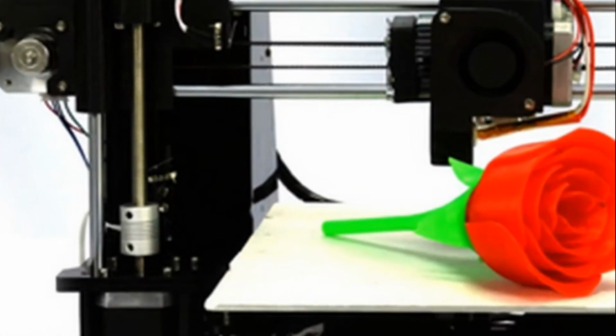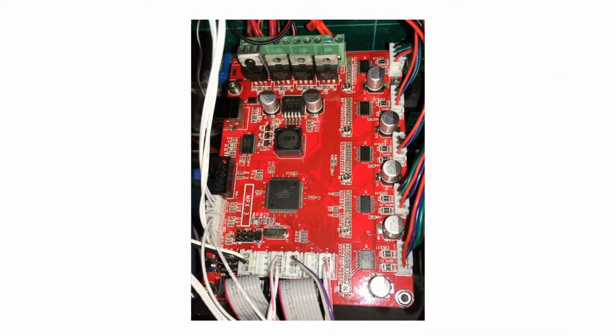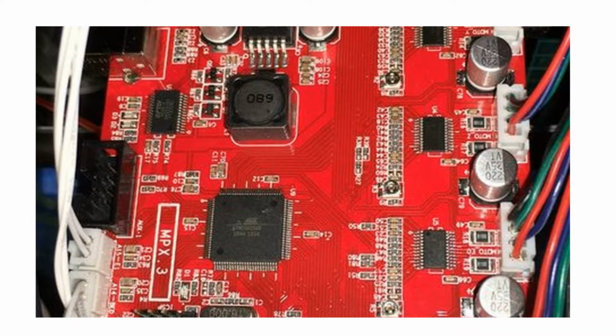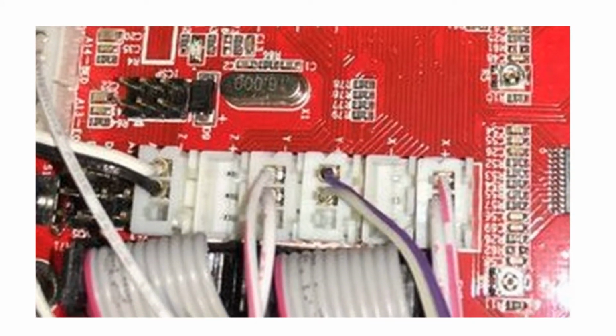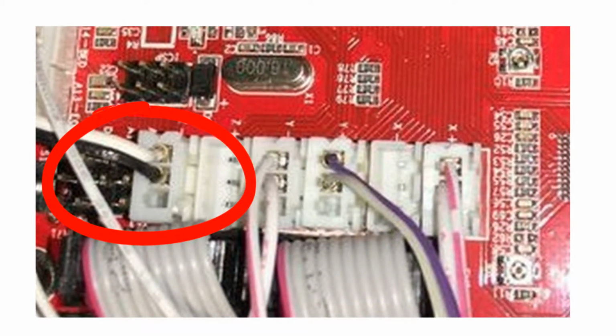Then we need to remove the current Z-limit configuration, which is a switch. We find the switch, remove it, and then pull the wire all the way back to the logic board and pull the actual connector. Don't discard it, we need it. We're going to modify that connector to use the white wire only.